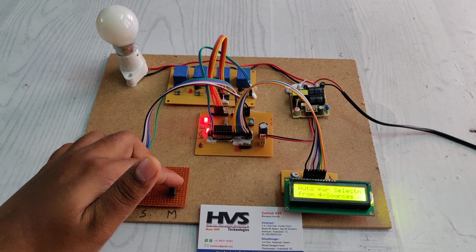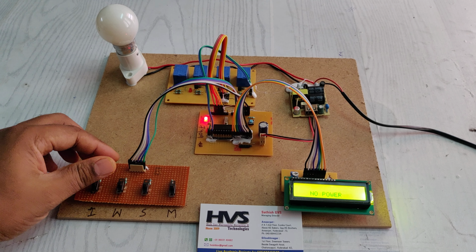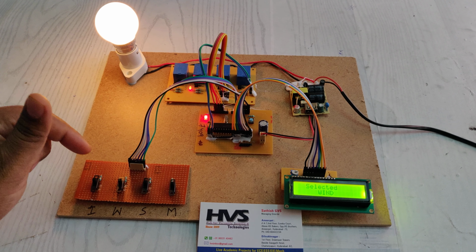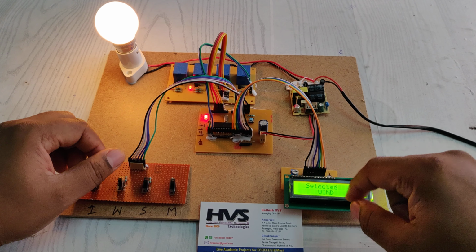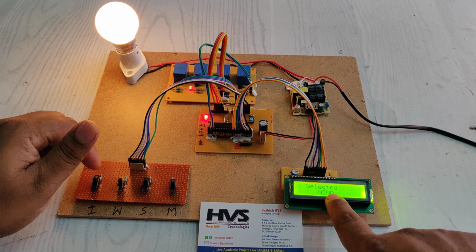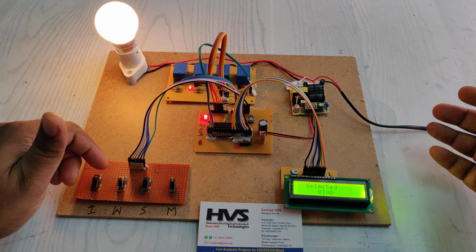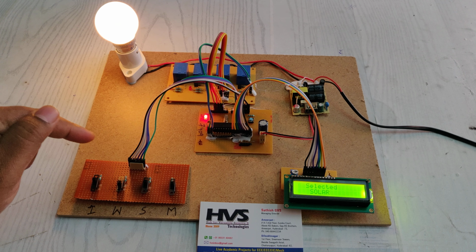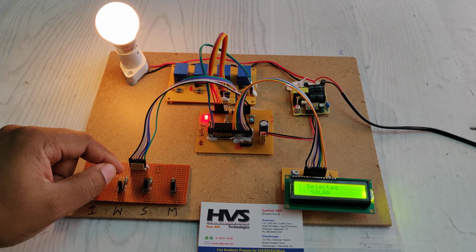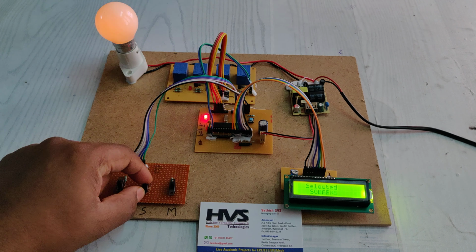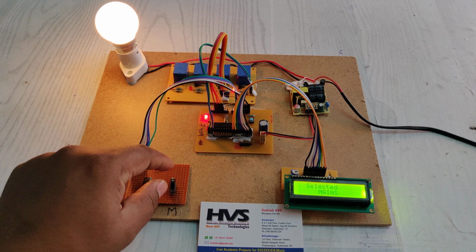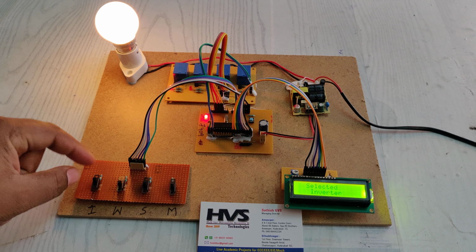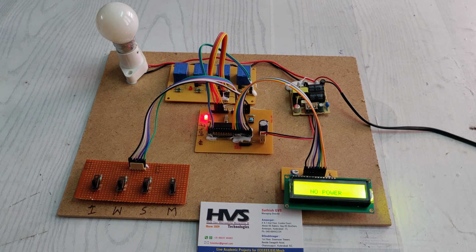With all switches downwards, there is no source available, so no power to the load. When all are available, as of now the wind is very irregularly available, but we selected the wind because it is low cost, then the remaining sources. When the wind is not available, it will go with the solar, the next cheapest power source. When the solar is not available, it will go with the mains, and when the mains is also not available, it automatically switches to the inverter. When all sources are not available, there is no power.